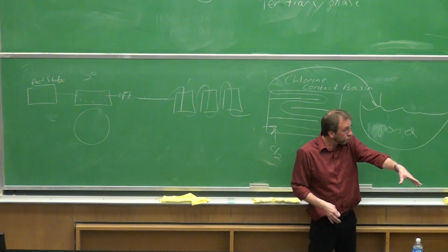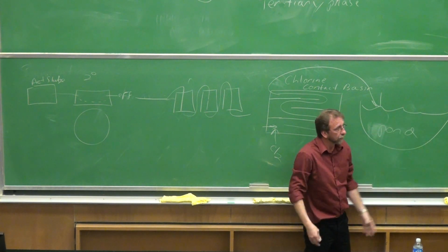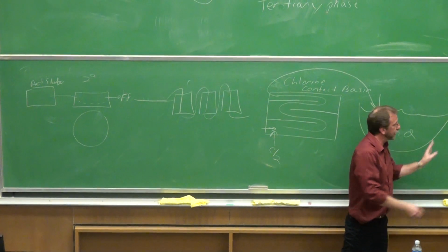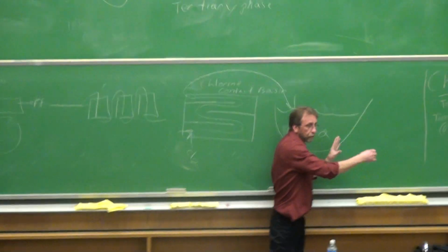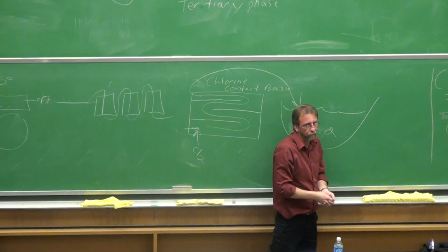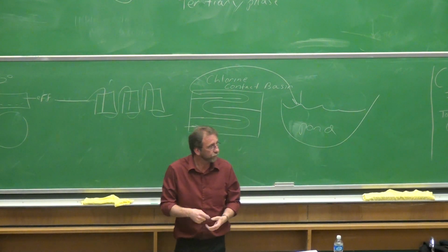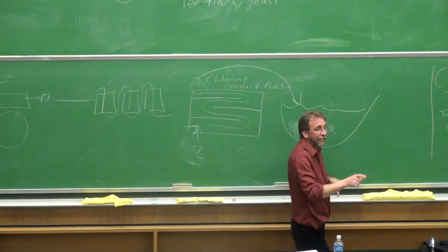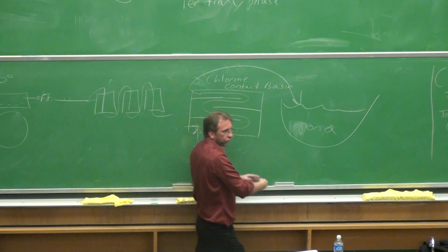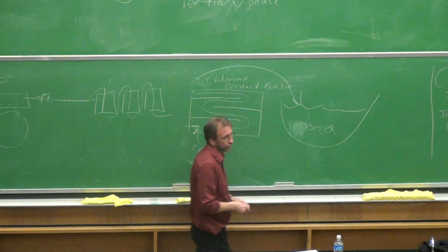But here's the thing about chlorine. It's very volatile, and it will off-gas given enough time. It's been determined, calculated, that by the time the water gets to the crops, most of the chlorine is dissipated. We go out regularly and sample water from these pumps to make sure that the chlorine is dissipated. And if it is too high, then adjustments are made over here to bring the levels down. And that's what's coming out of the purple pipes. Exactly.